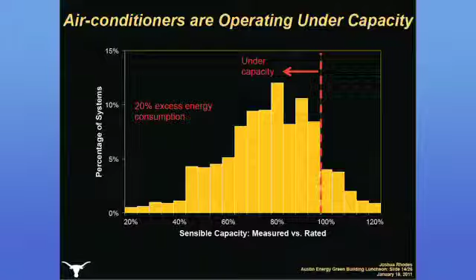In sensible capacity measured versus rated, we took 80% of the nameplate efficiency and called that the sensible rated capacity, and then compared that to the temperature difference across the coil and the airflow. Now the airflow, again, was not measured, it was just assumed, so take this with a grain of salt. But we look at the possibly up to 20% excess energy consumption from air conditioners operating under capacity. This can be fouled coils, this can be poor refrigerant charge. That's typically a big one.